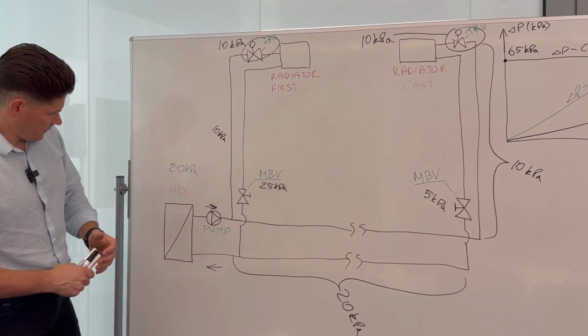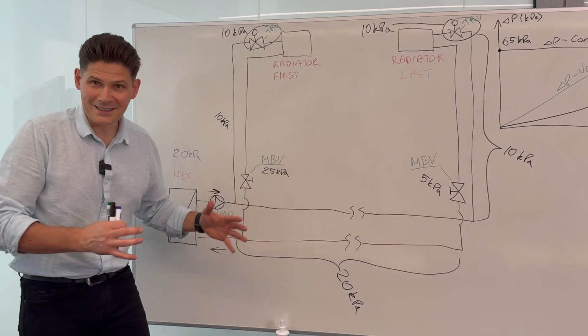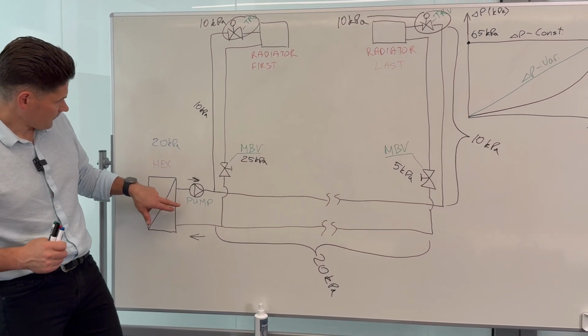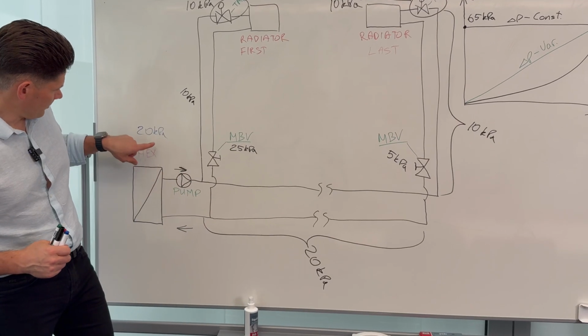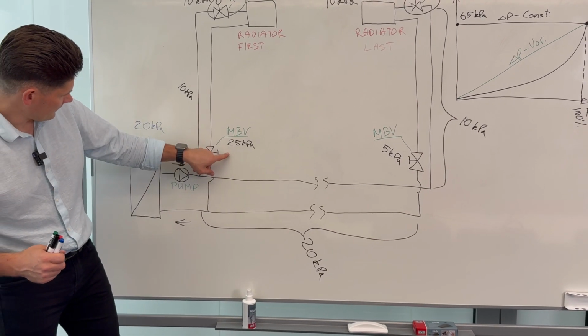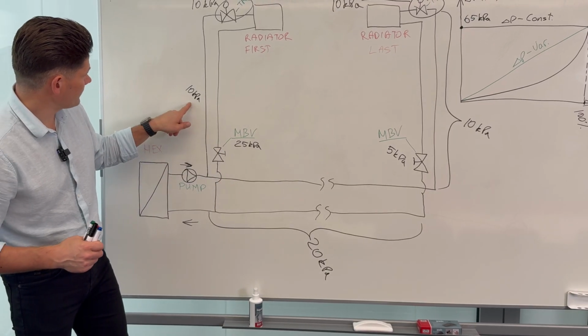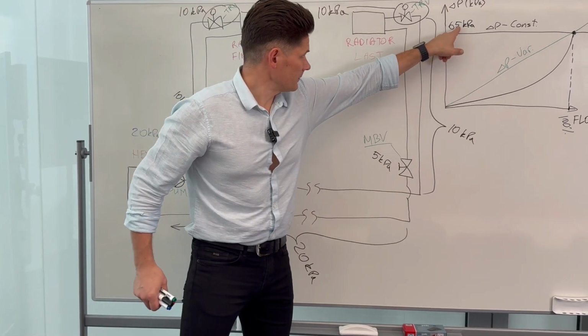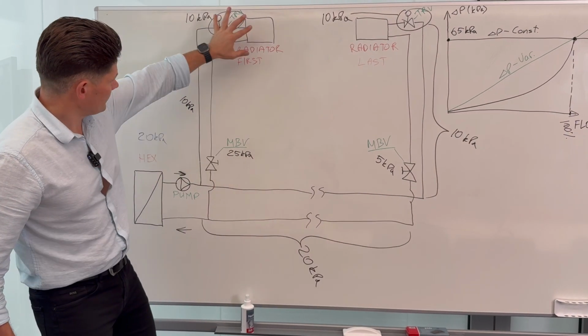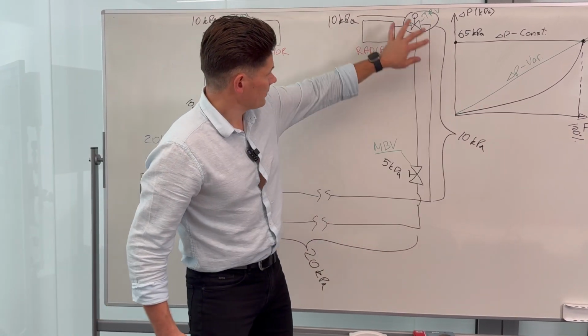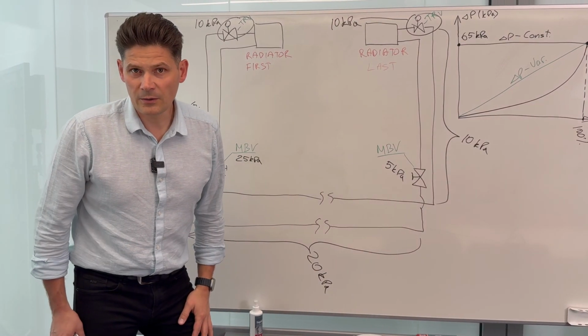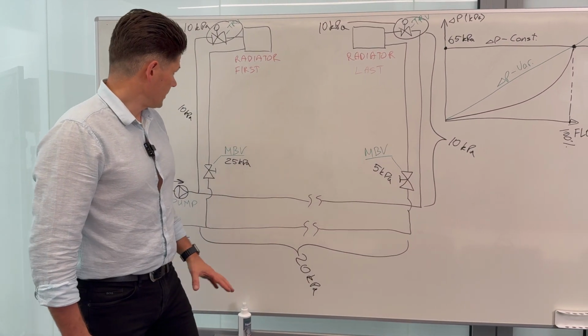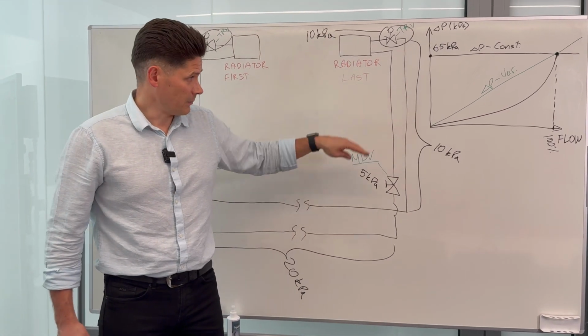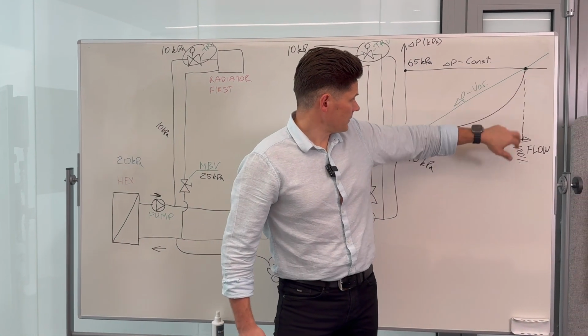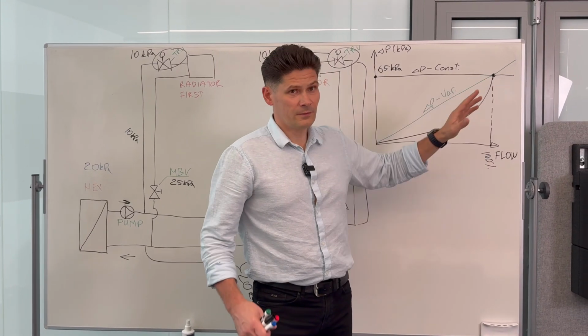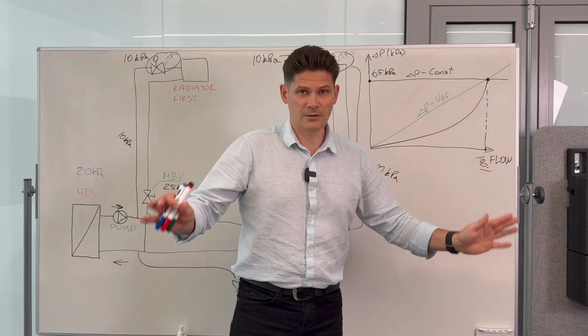Okay, let's calculate it if I balanced it correctly. It should be also 65 kilopascals, so 20 plus 25 will be 45, 55, 65. So this means this circuit is 65 and this circuit is also 65. So my system now is commissioned and I have the right flows where I need. My system is working at 100%, and everything is balanced, commissioned, and runs smoothly.